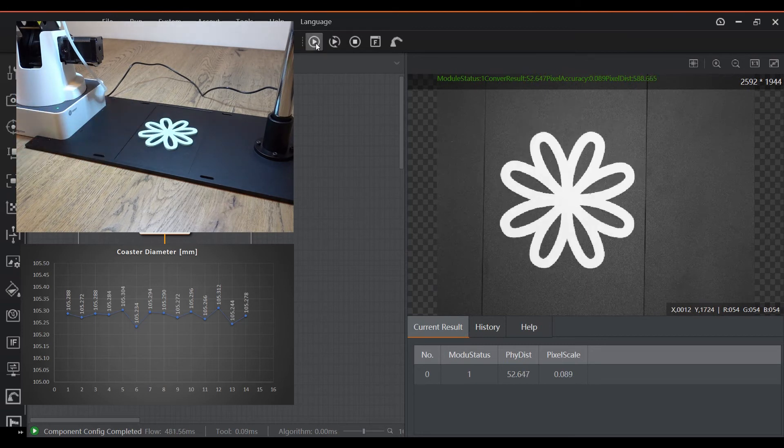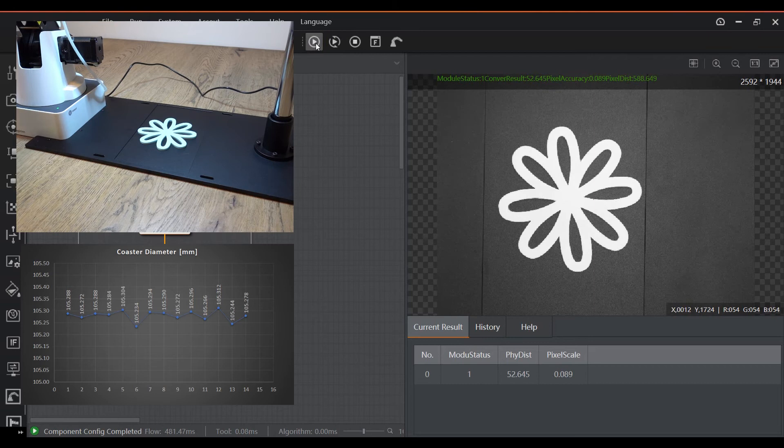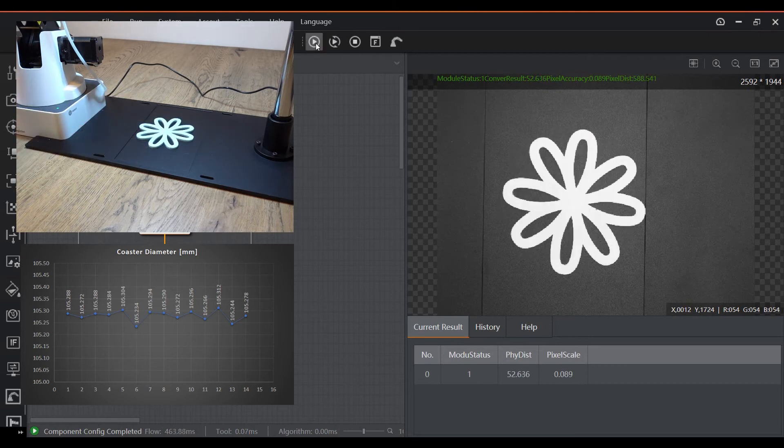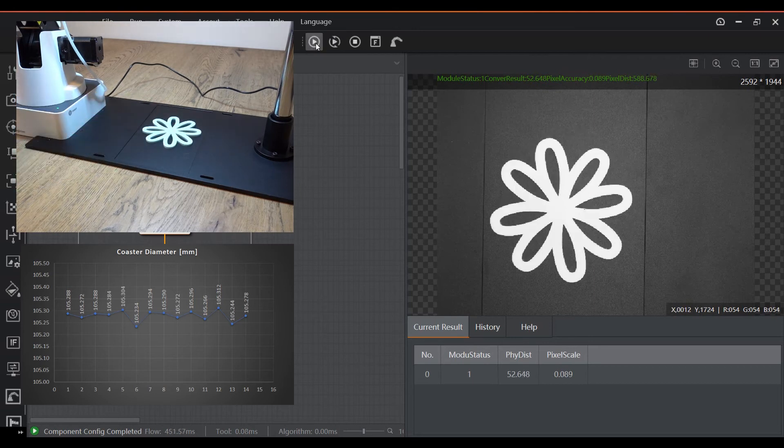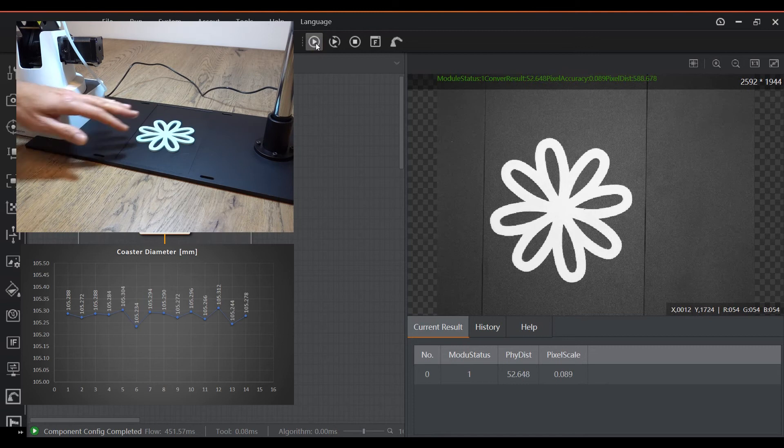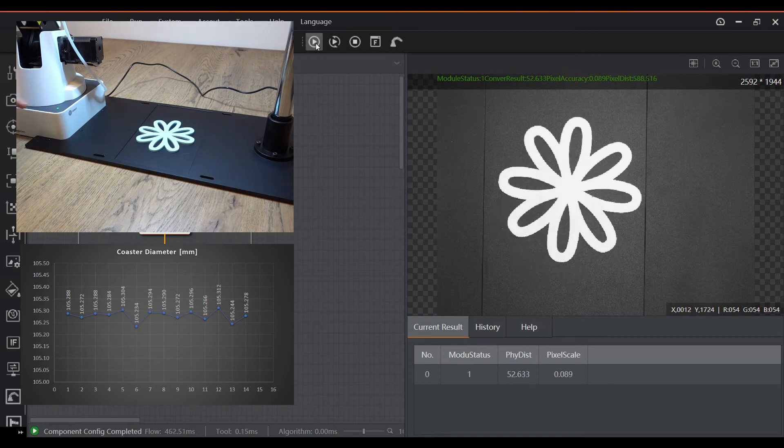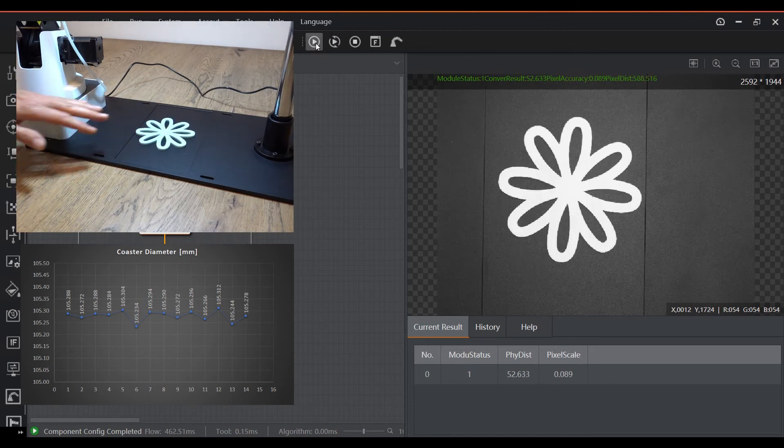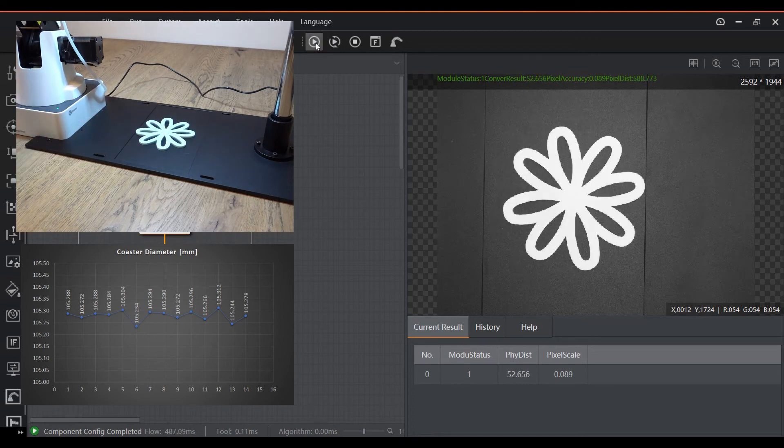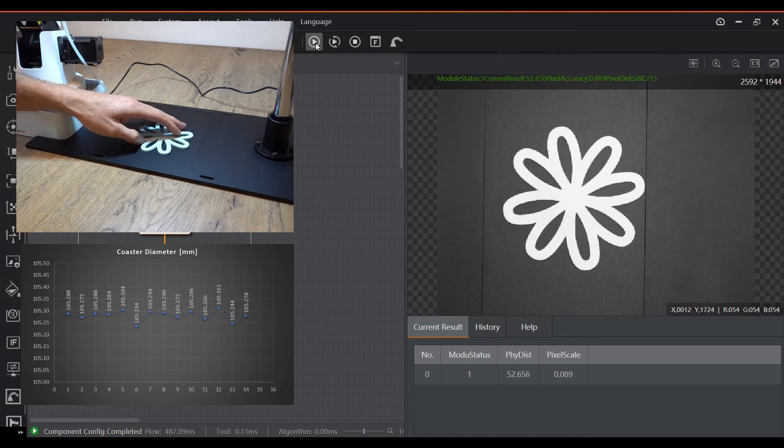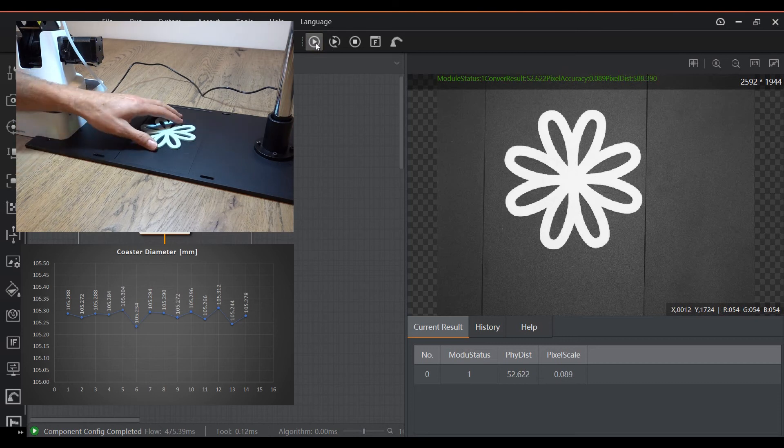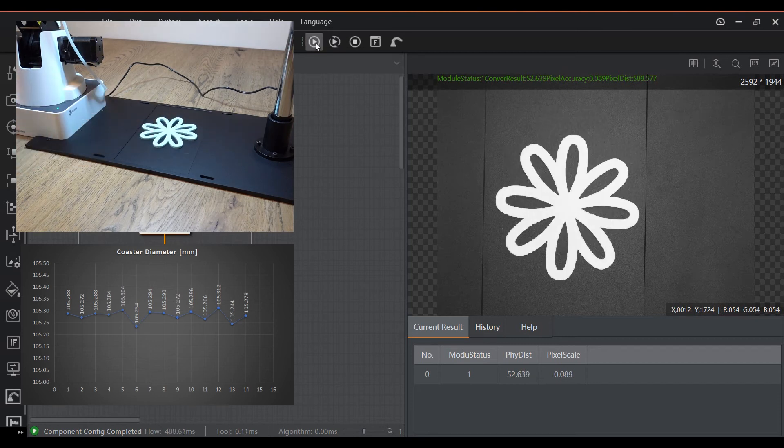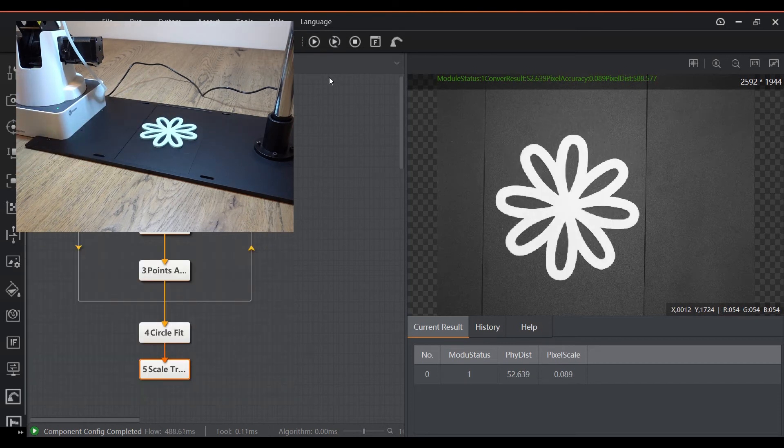The standard deviation of the measurements is only 22 microns, which is quite good actually. It has to be noted that the repeatability of the system is dependent on many factors such as contrast, lighting, how the system was trained to find features, etc. So your mileage may vary.